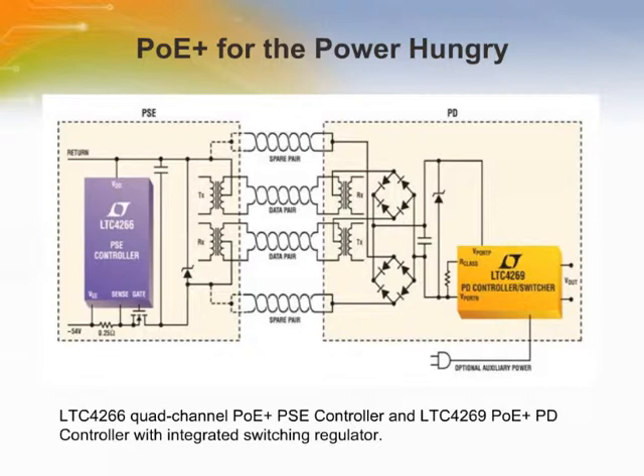The Linear Technology LTC 4266 is a fully compliant 802.3 AT quad PSE controller and is backward compatible with the popular 802.3 AF standard. Not only does it provide PDs with power levels mandated by the new standard, but it also allows users to mix and match up to 4 PoE and PoE Plus PDs. To be 802.3 AT compliant, a PSE must provide 30 watts at the output of the PSE connector, so that after cable losses are accounted for, 25.5 watts is available to the PD. The LTC 4266 provides the 30 watts while drastically minimizing heat dissipation.